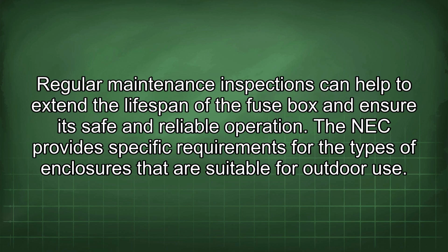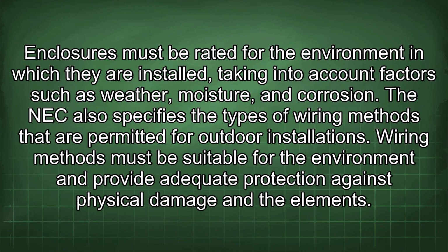The NEC provides specific requirements for the types of enclosures that are suitable for outdoor use. Enclosures must be rated for the environment in which they are installed, taking into account factors such as weather, moisture, and corrosion. The NEC also specifies the types of wiring methods that are permitted for outdoor installations. Wiring methods must be suitable for the environment and provide adequate protection against physical damage and the elements.